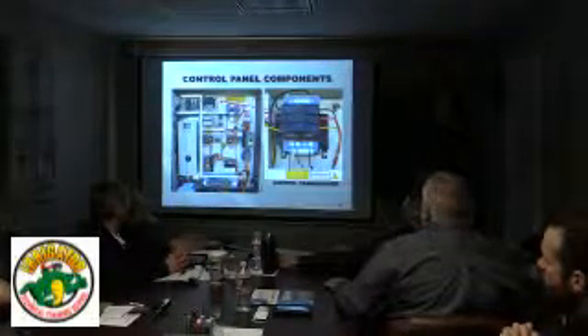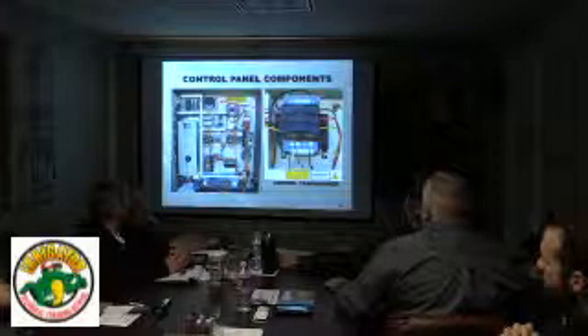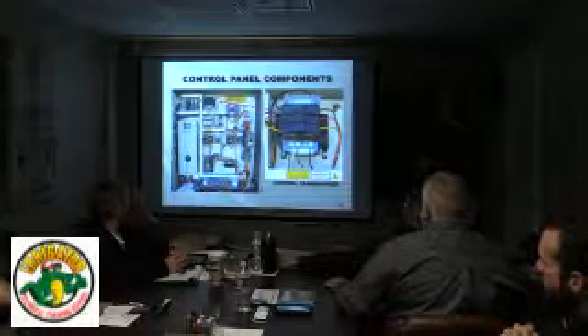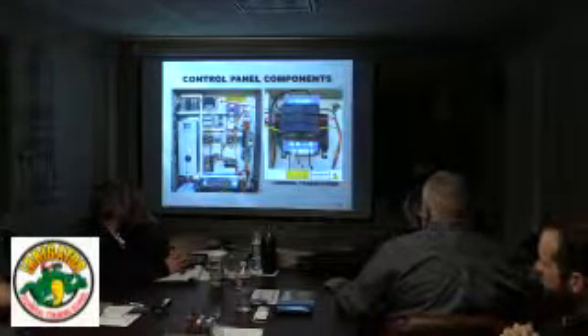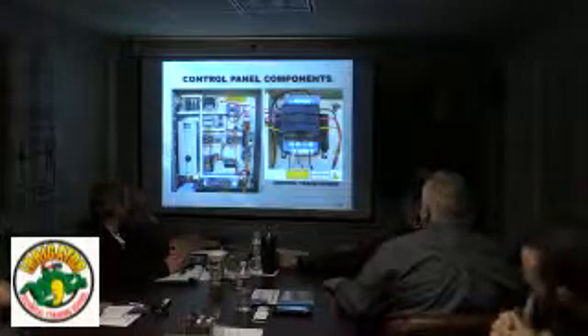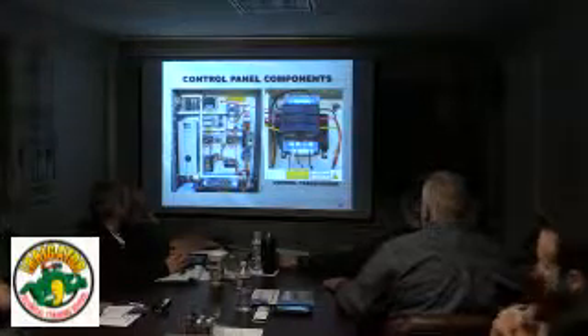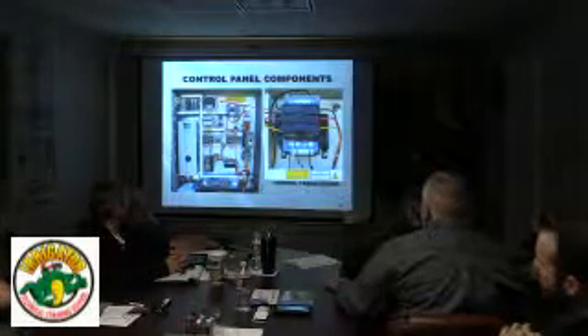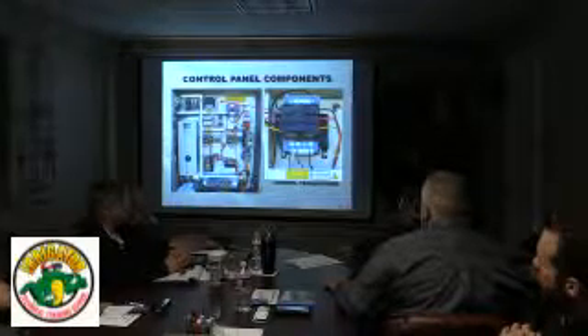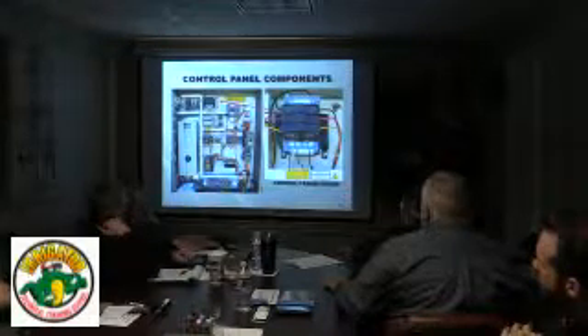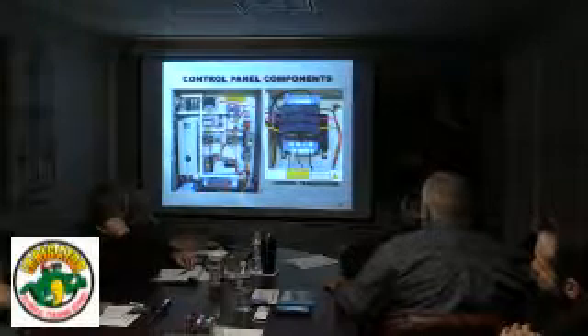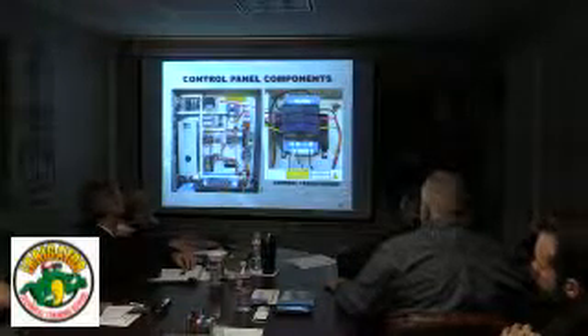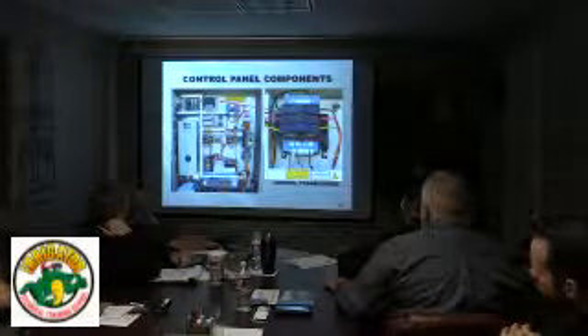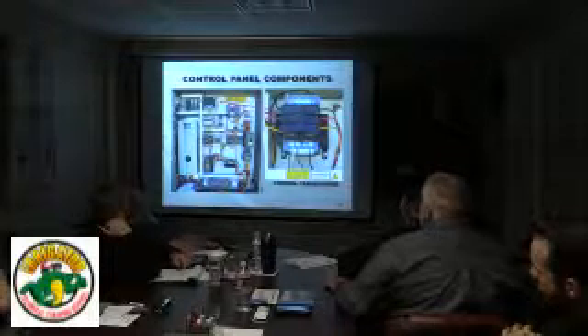So we'll look at the control transformer first. Notice that there's 3 fuses on here. They're labeled F1, 2, and 3. These kind of serve a dual purpose. You'll notice that our primary 480 volt input on the primary of the transformer comes off of fuse 1 and 3.